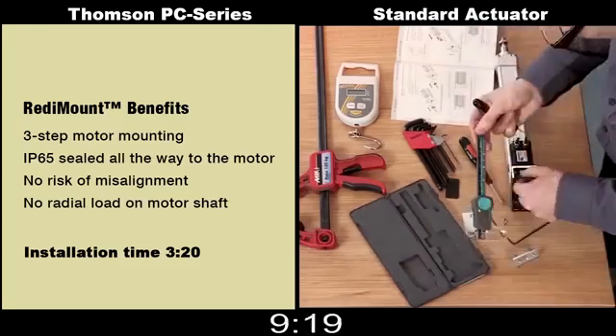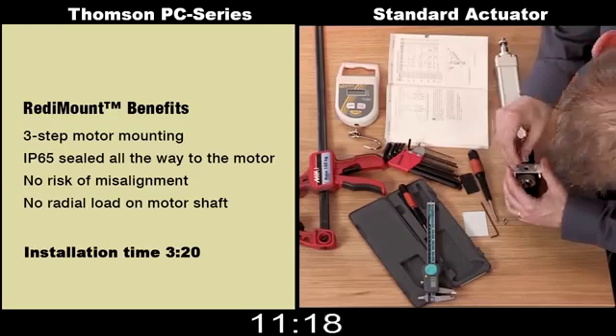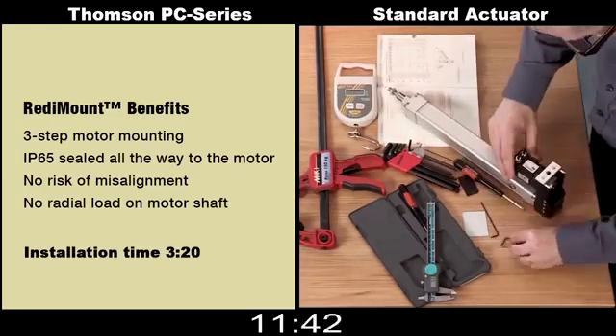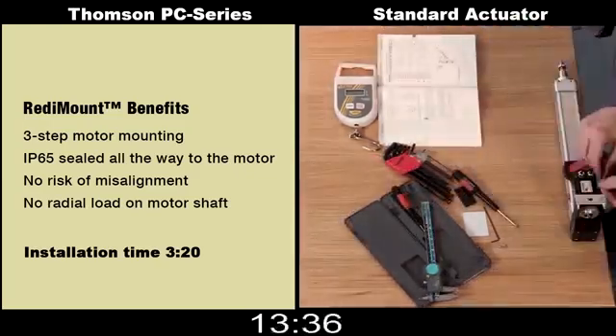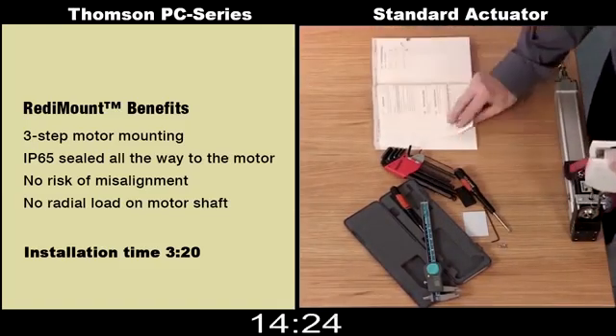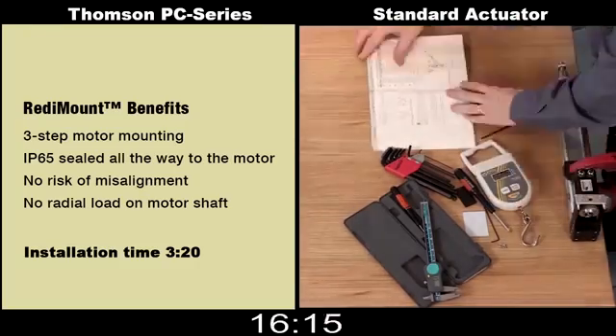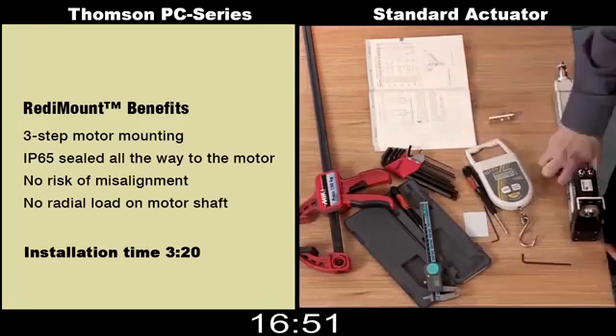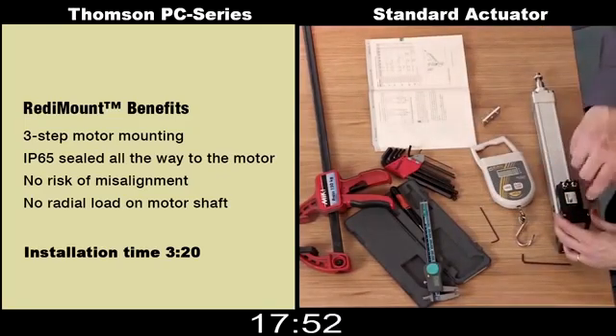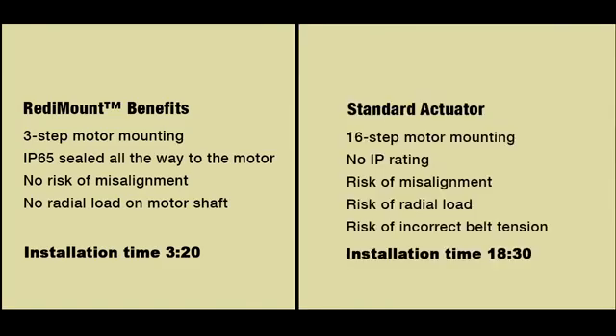It comes designed with a dual or straddle mounted bearing system, eliminating any risk of misalignment and ensuring that the shaft of the motor will not be subjected to any radial loads — important not only for noise, but also to avoid shortened life of the motor. Furthermore, not only is the actuator itself IP65 rated, but the PC series RediMount is also IP65 all the way to the motor, providing a robust piece of equipment for harsh environments where wash down or cleaning is required.